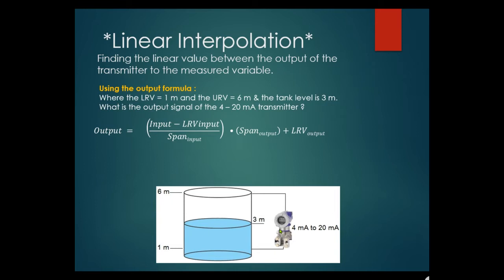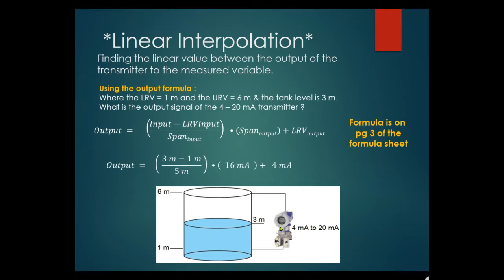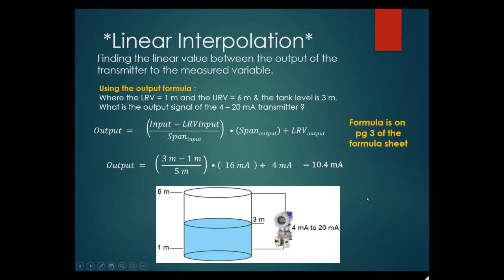The formula is on page 3 of your formula sheet. Working through the example: input is 3 meters minus LRV of 1 meter, divided by span of 5 meters, times output span of 16 milliamps, plus LRV of 4 milliamps — giving 10.4 milliamps. These calculations should become standard for you. You can also go vice versa using the input formula, which is just a transposition.